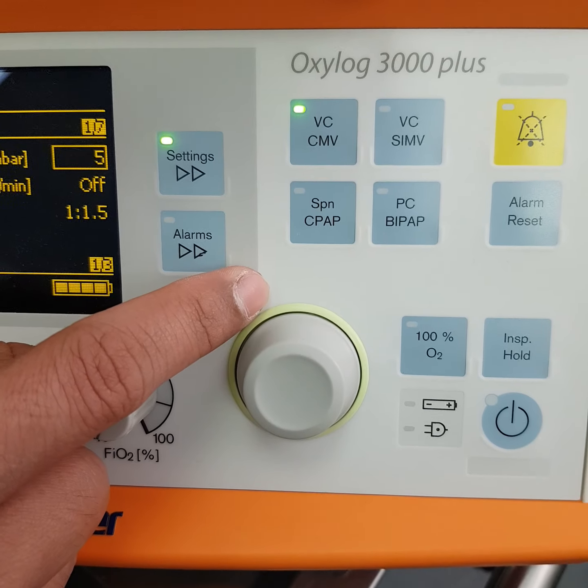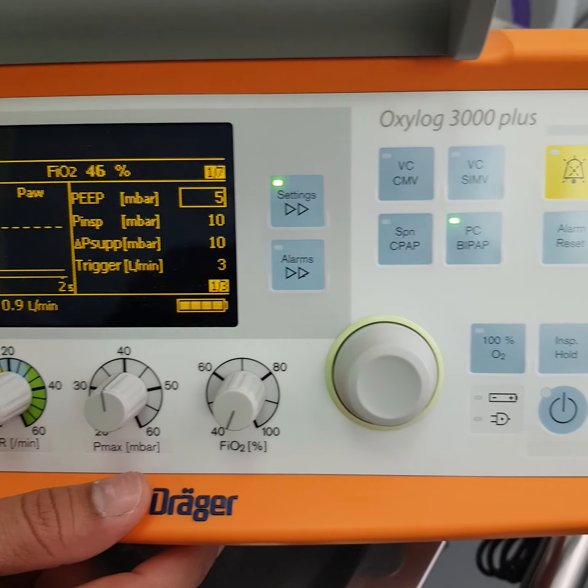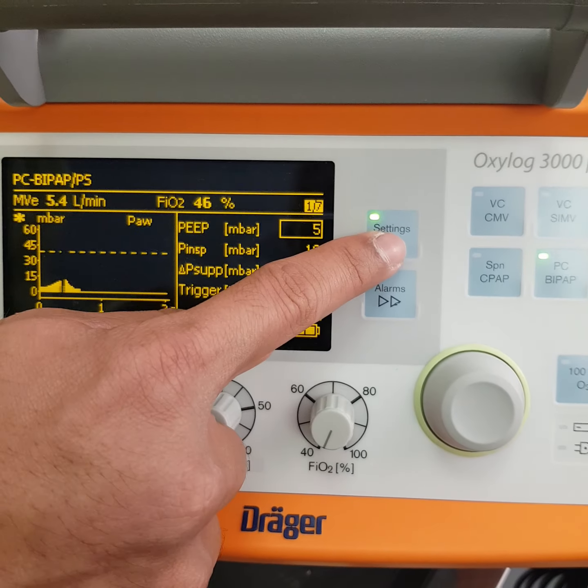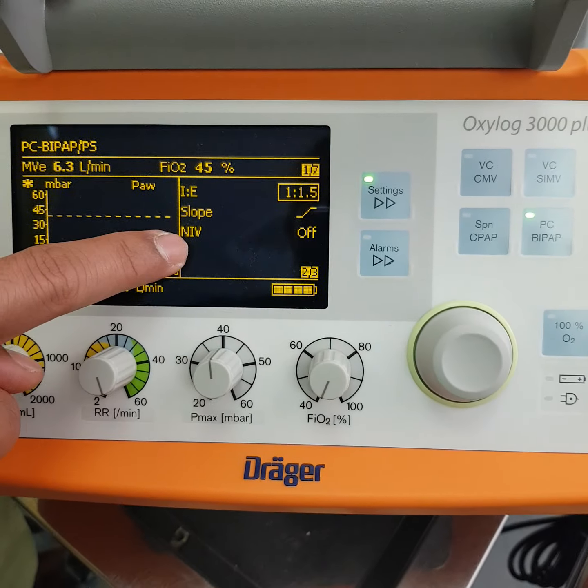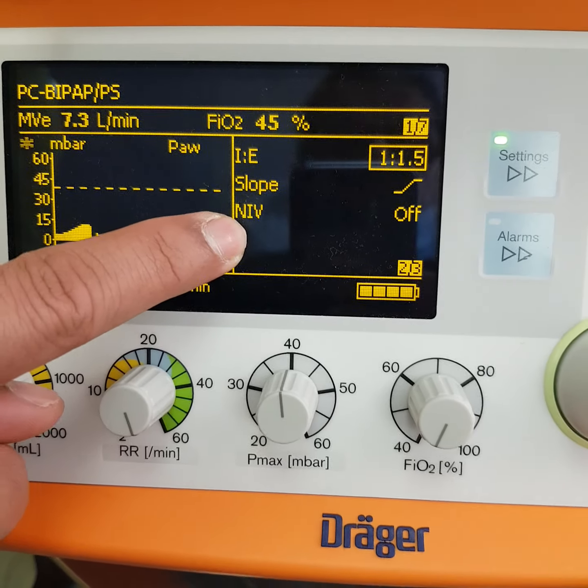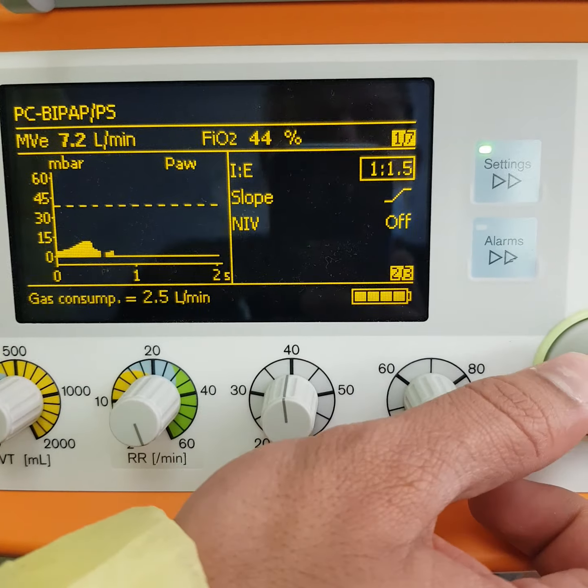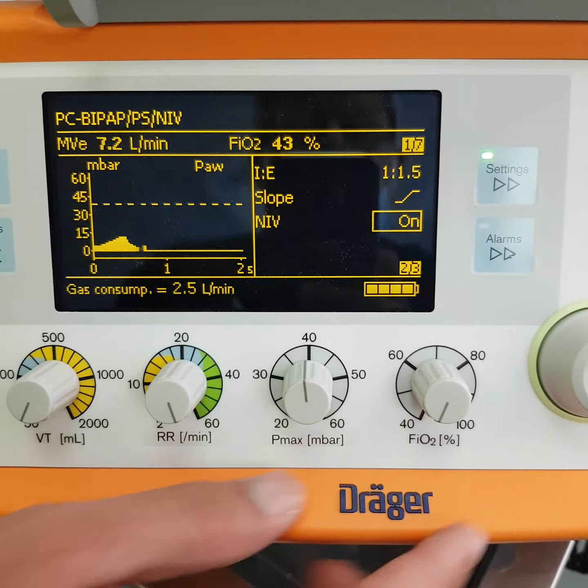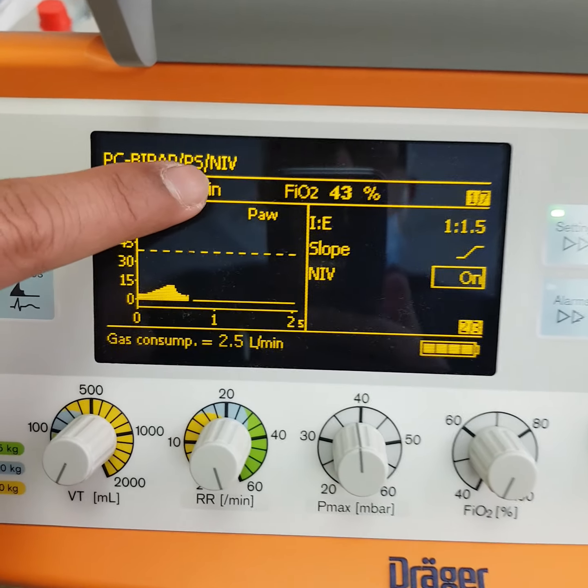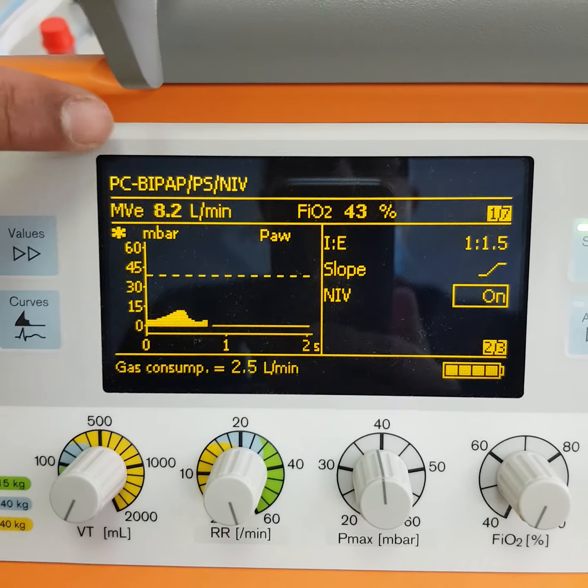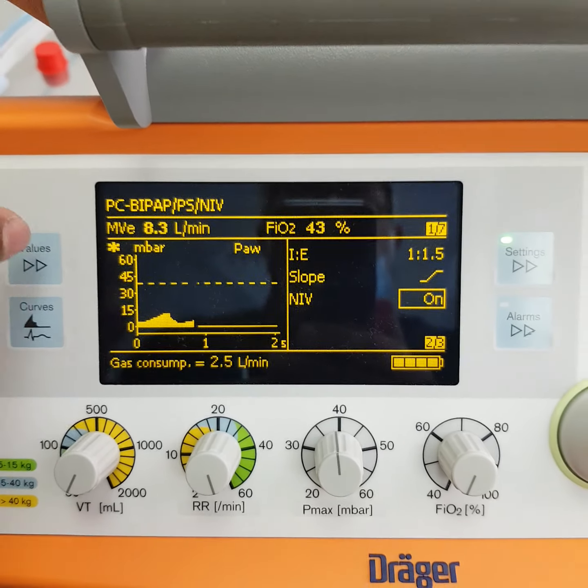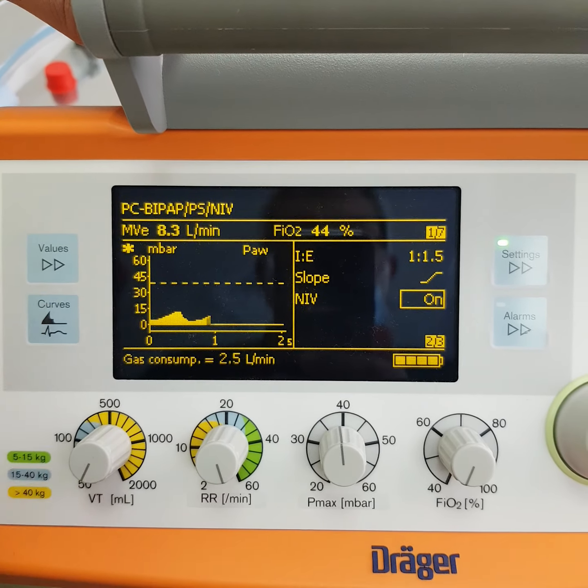So as I mentioned, these two modes can be used as non-invasive ventilation. For example, if you want to use BiPAP as non-invasive, just select the mode. You can go to the settings, and you will see in the second screen the NIV option, which is off right now. If you make it on, the machine will know that you are using it for non-invasive ventilation.